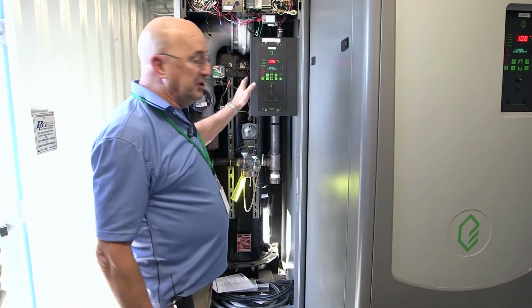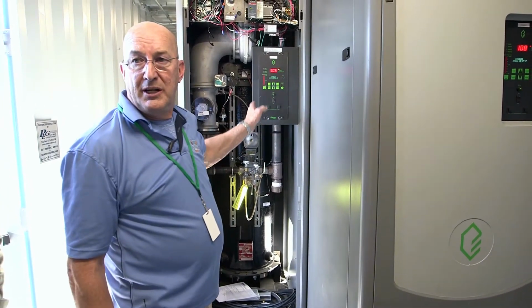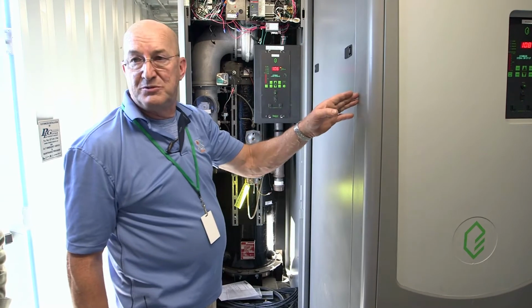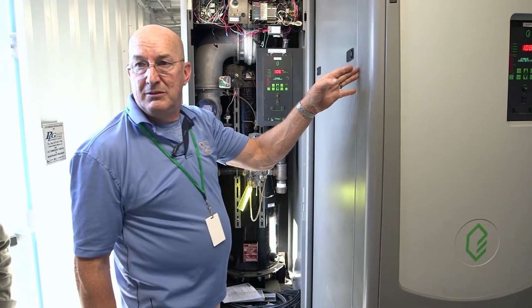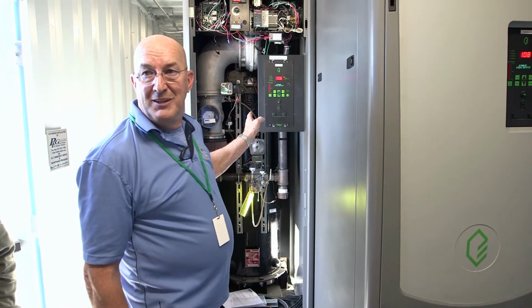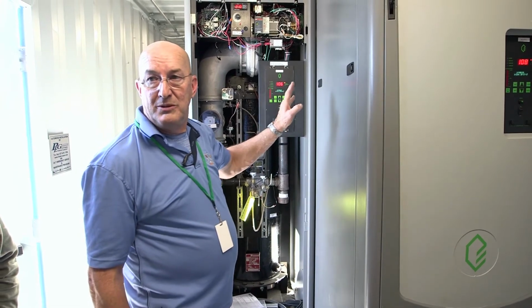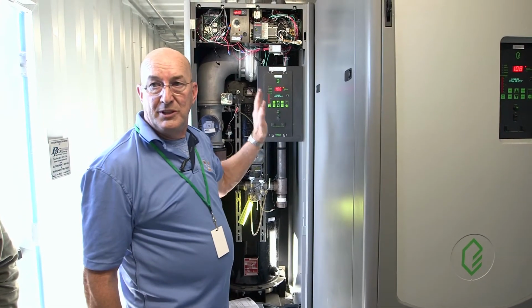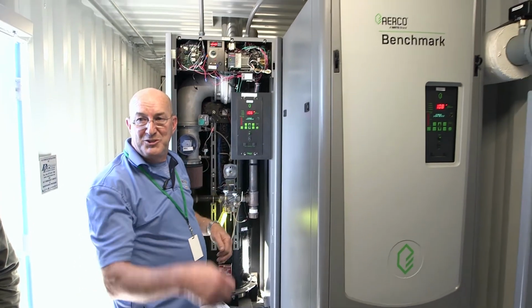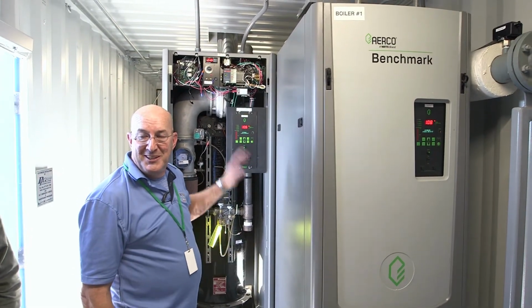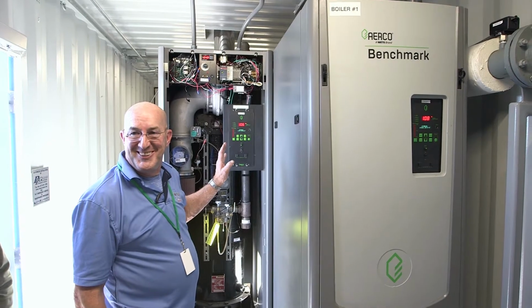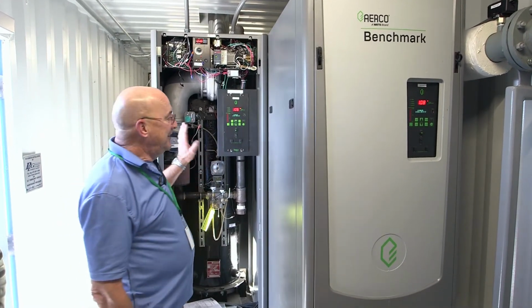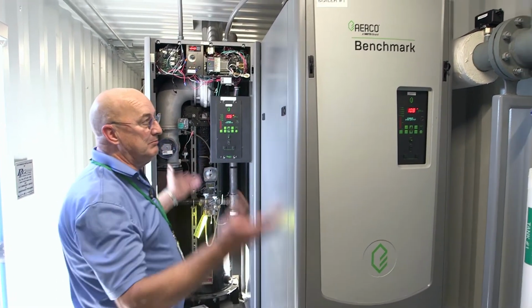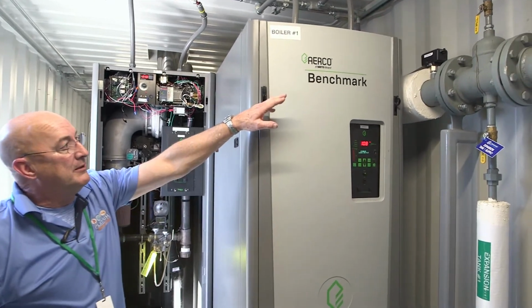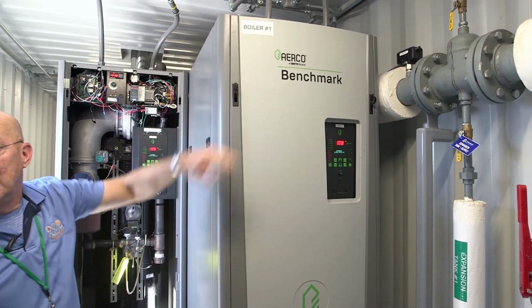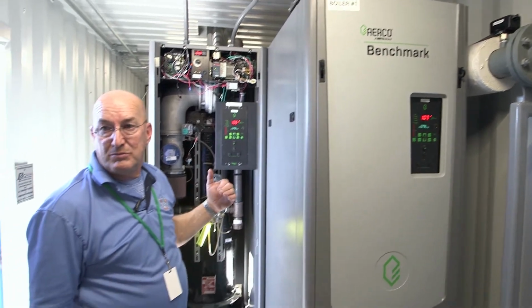The main control panel in here will also say, you know what, I have too much runtime, you don't have as much runtime. I'm going to run you today, and I'm not going to run. It's got a brain of its own, and it decides what it's going to do and alternates it. No more worrying about shutting the switch off or turning the switch on. It thinks ahead of us. It goes in the lead lag, and they rotate and they go up and down according to the header temperature sensor there. That's what's telling the boilers what to do.